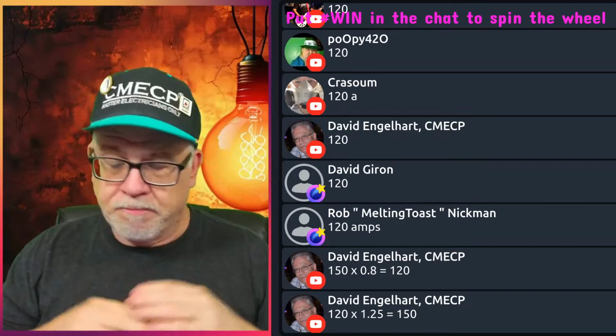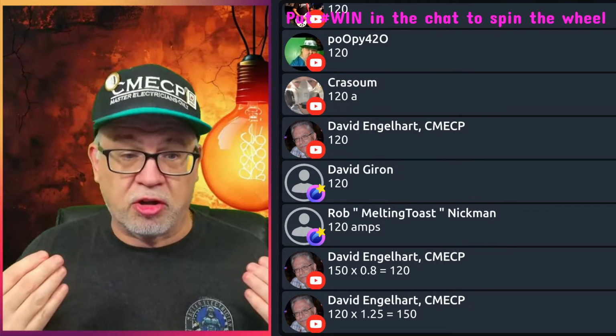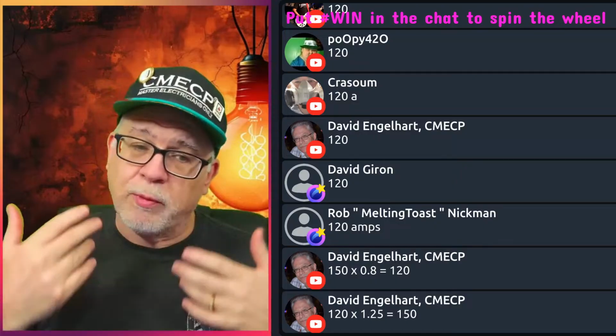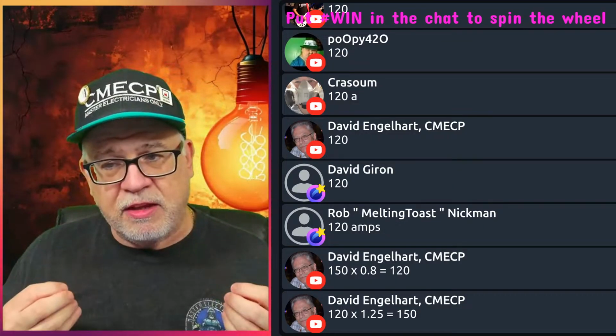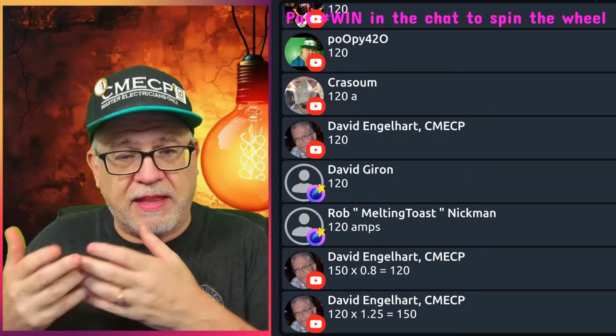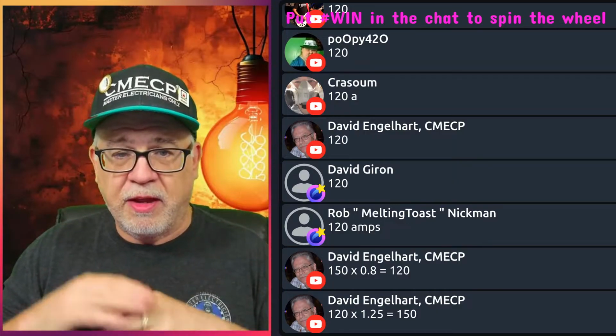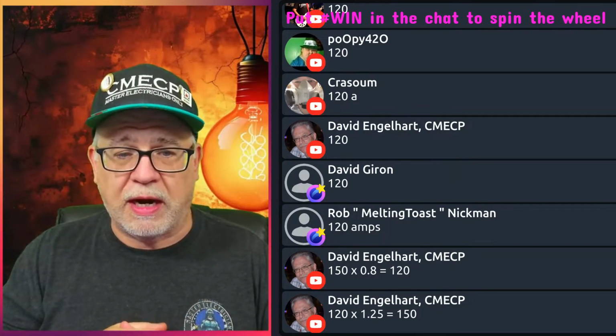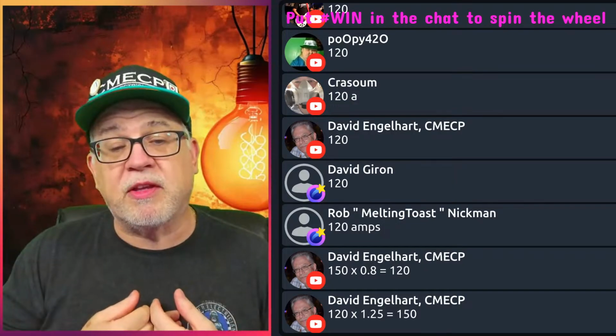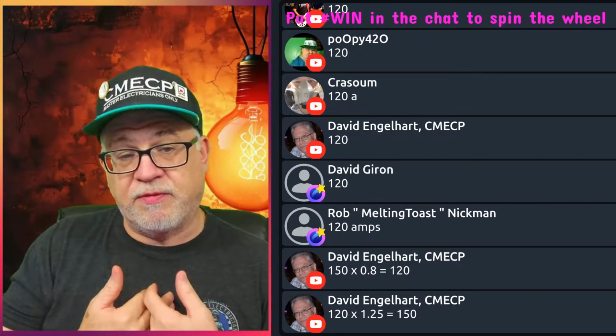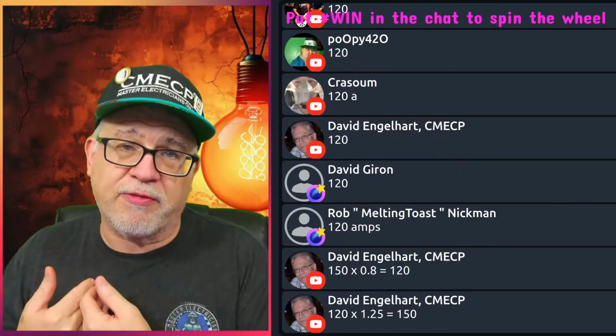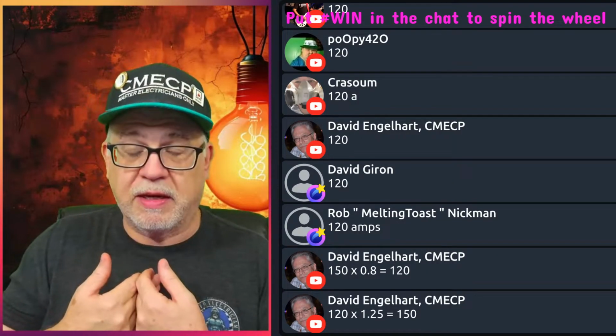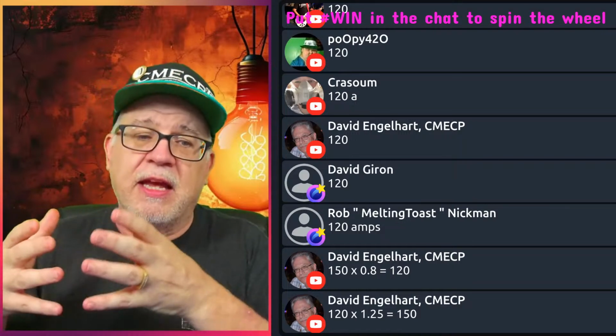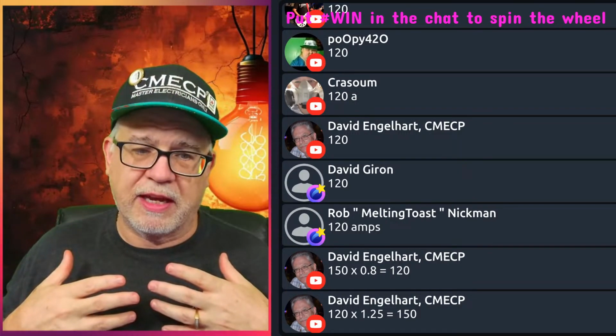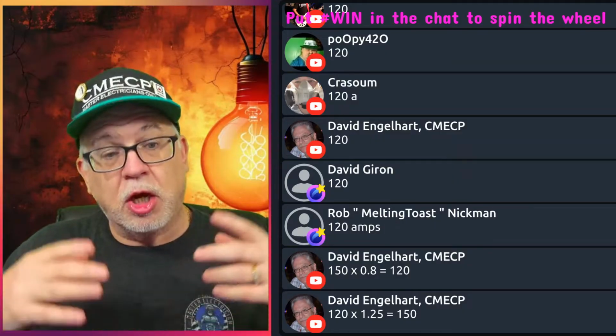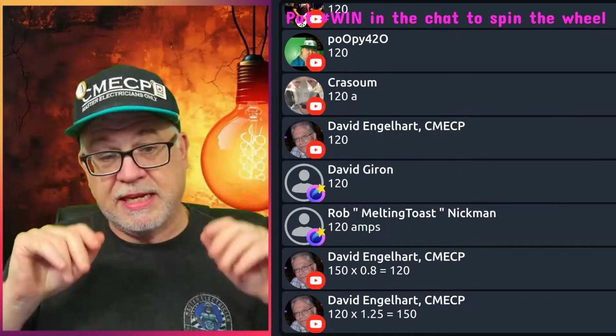Did the load change? No, it's still 120 amps of continuous load. The reason we do the 125% is we're building in that fudge factor, that heat buildup factor, from the design and testing of breakers and wire. When we size wire at 125%, we're really helping out the breaker manufacturers, because our wire acts as a heat sink, pulling heat away from the termination on the device. So manufacturers of breakers out there, you're welcome, we've got you covered.